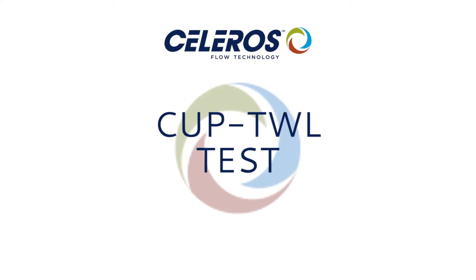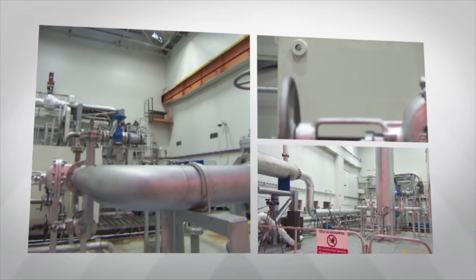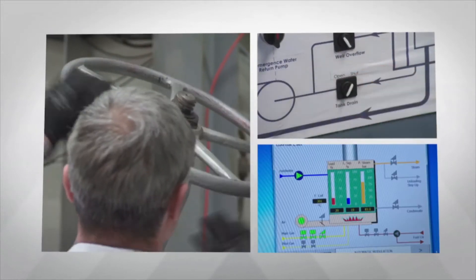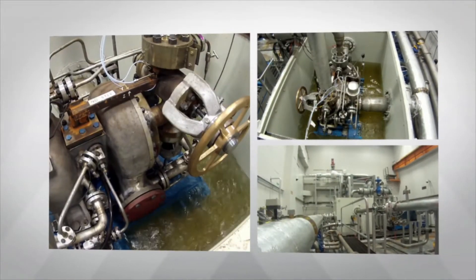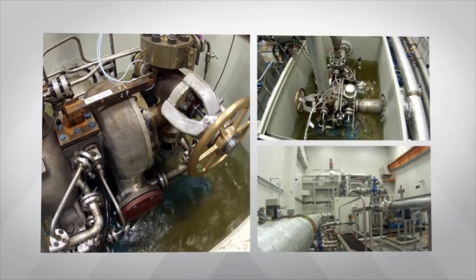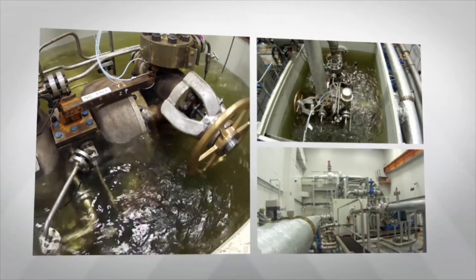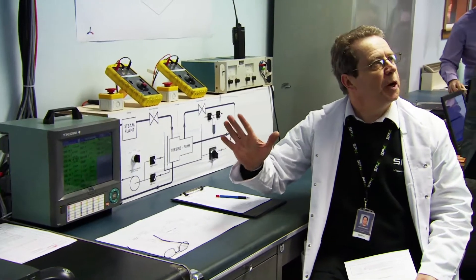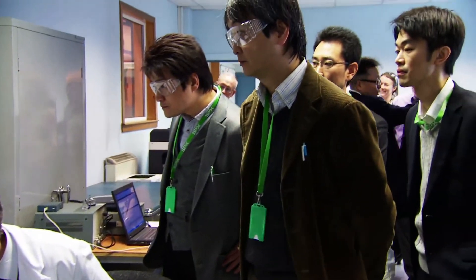Clyde Union Pumps successfully completed two eight-hour submergence tests of the TWL at the facility in Glasgow, Scotland. Test engineers installed the TWL into a purpose-built tank designed to simulate flood conditions. The test began with flooding the TWL with cold water, starting it with design steam conditions, and conducting a series of performance tests and an emergency stop-start while submerged.